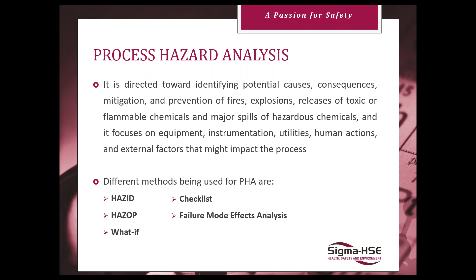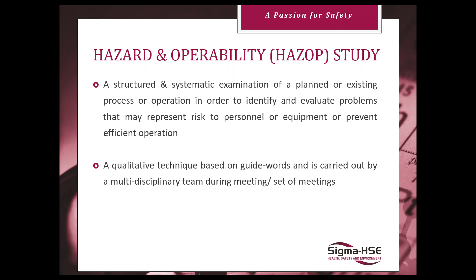So your hazard and operability study is really the most structured method for the PHA. You're looking at it on a piece of equipment by piece of equipment basis, each parameter for that designed intent equipment and how it can fail. And that gives you your most comprehensive understanding of what you have, what your issues may be, and it's all based on your guide words. And you want to have, like Andy was saying, a multidisciplinary team. You don't have a single individual, you have a facilitator, you have design engineering, test engineering, safety, maintenance, operations, as many groups involved with the process as possible to make sure you're getting that high level view.